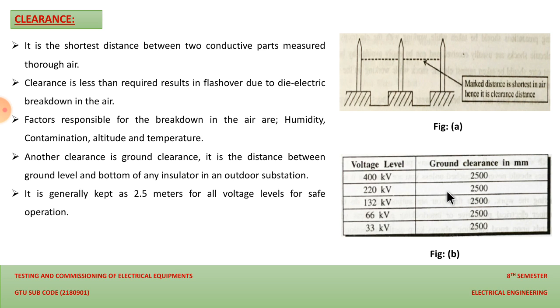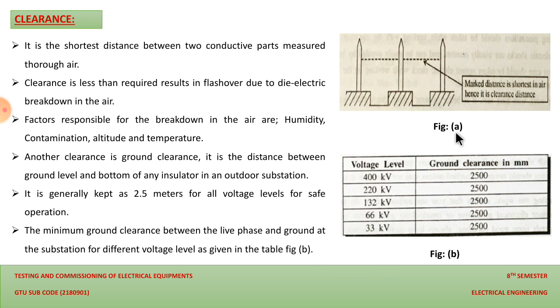Because of this, if we keep this distance, then we can reduce the chances of flashover due to dielectric breakdown in the air. So this is called clearance in the electrical system. So the minimum ground clearance between the live phase and ground at the substation for the different voltage levels is shown in this table, which we have already discussed. So this is what clearance is, and if we keep a proper clearance between two electrodes, then we can reduce the chances of flashover due to dielectric breakdown in the air.